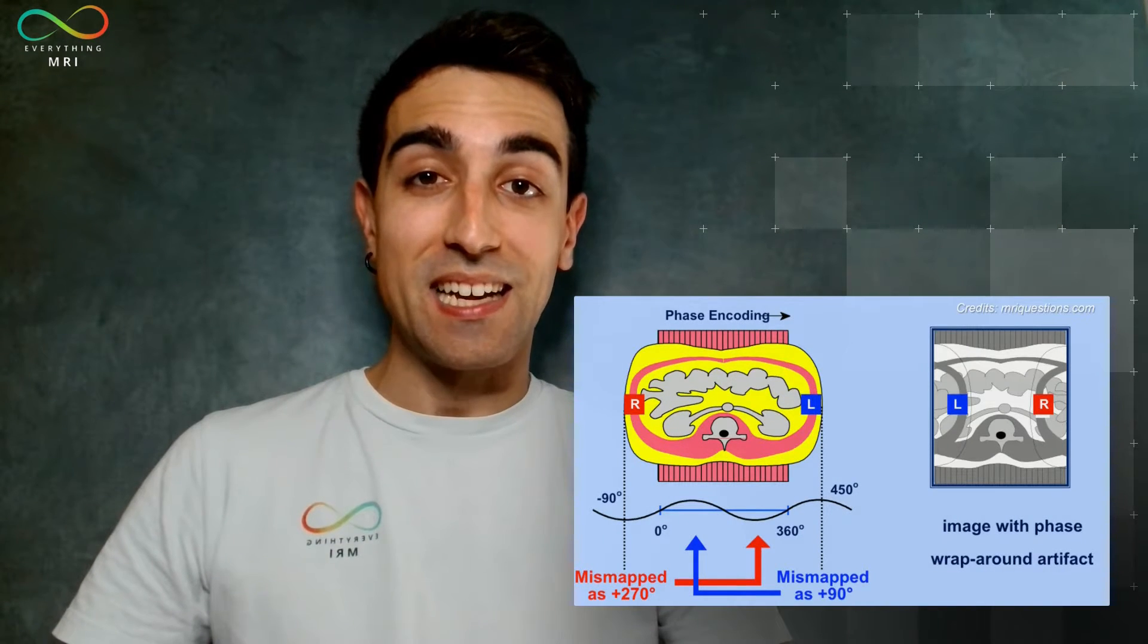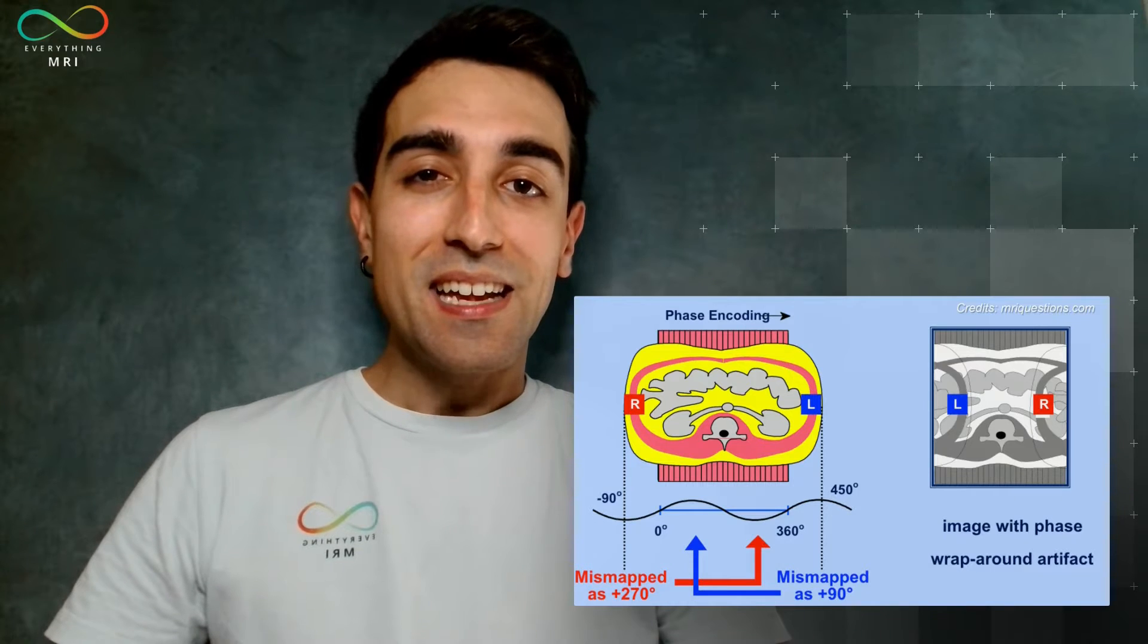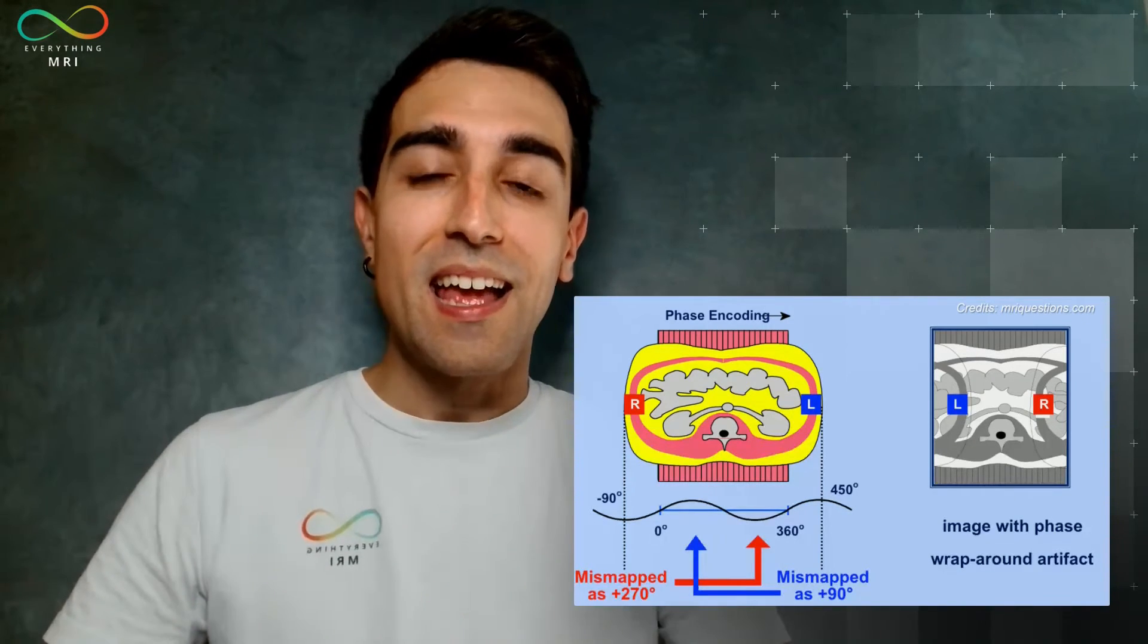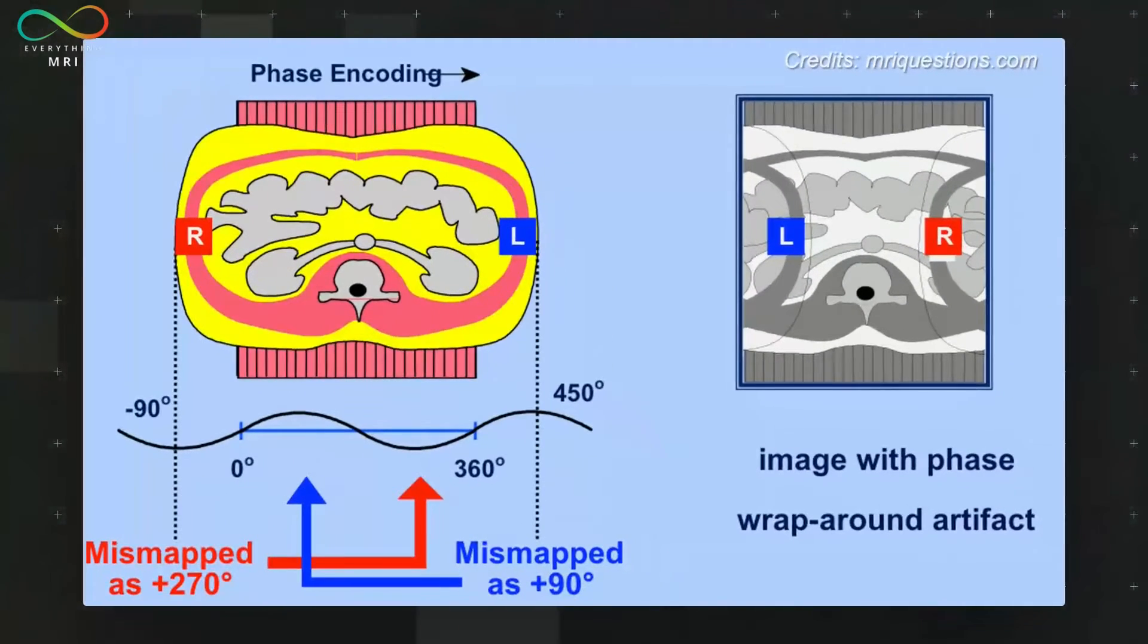A specific type of aliasing is better known as phase wrap around artifact. This occurs when the anatomical dimension of an object exceeds the defined field of view. Essentially portions of the object outside the FOV are incorrectly interpreted, facing therefore a phase shift and ending up folded over into the images from the edges.